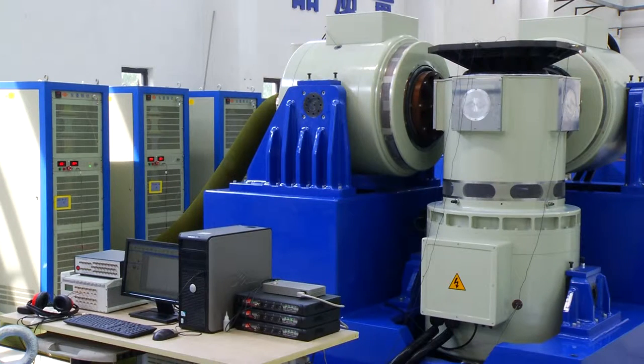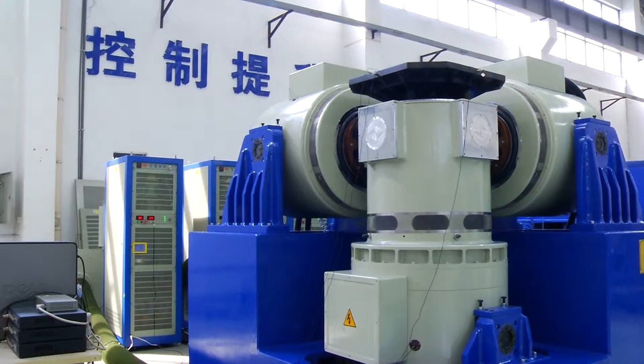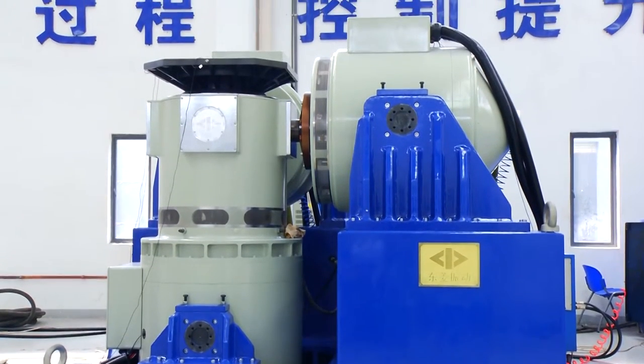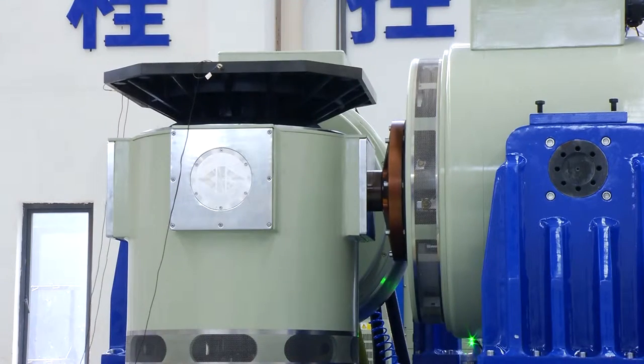This system is a 60 kN three-axis test system. It uses three sets of 60 kN shakers working together on one table to achieve vibration in three directions simultaneously, which can simulate the working environment more realistically.